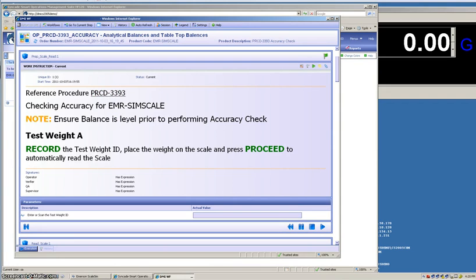The operator is reminded to ensure that the scale is level prior to performing the accuracy check, and that they're going to be using test weight A. The instruction is to record the test weight, place the weight on the scale, and press proceed. Now, a lot of times with paper tracking, manual transcription is a big cause of errors. What we're going to use here today is barcoding in order to facilitate data entry for the operator.